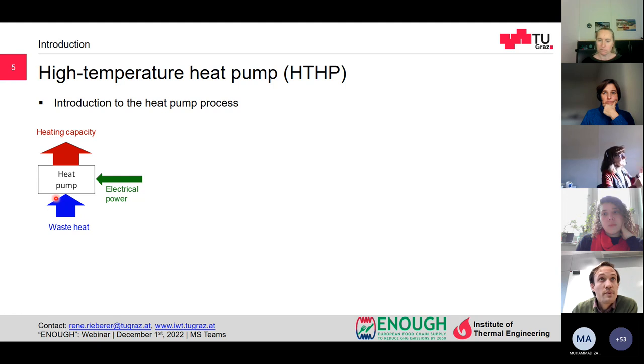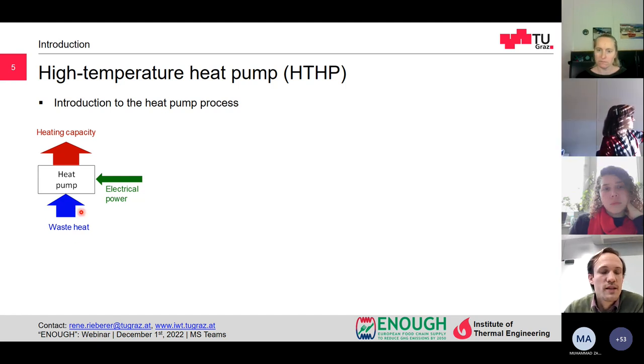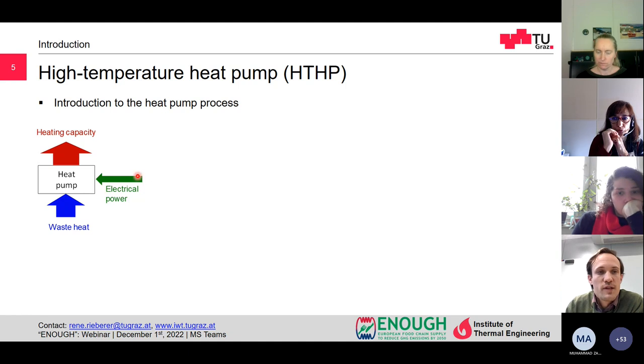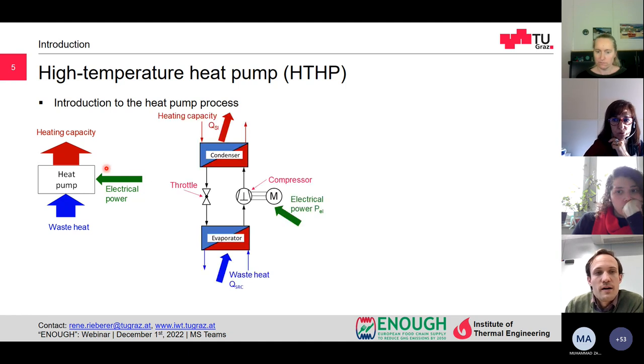So a high temperature heat pump can utilize waste heat on a low temperature level and lift it up to a temperature level suitable for processes, and can supply this heat, for example, in our case, for a cleaning in place system, by a small amount of electrical power.